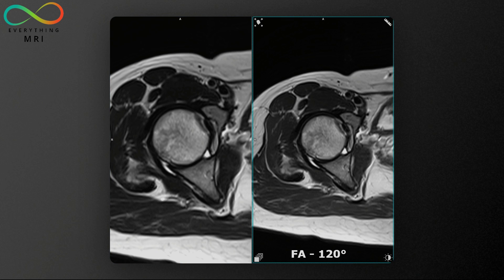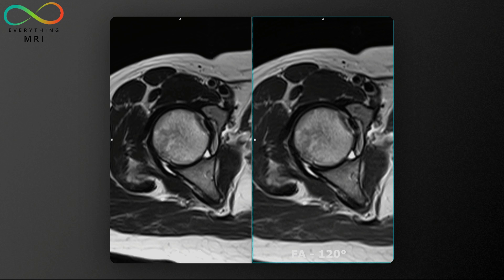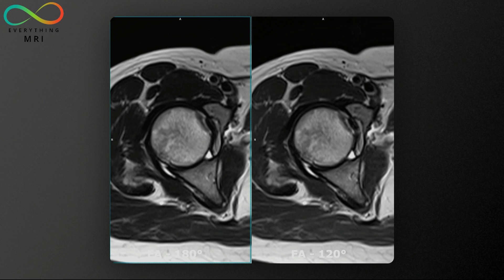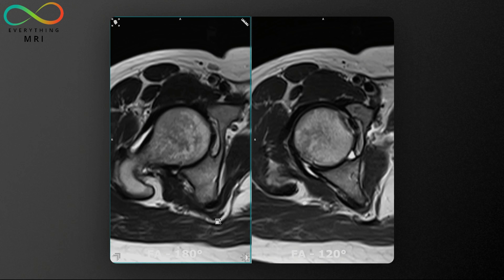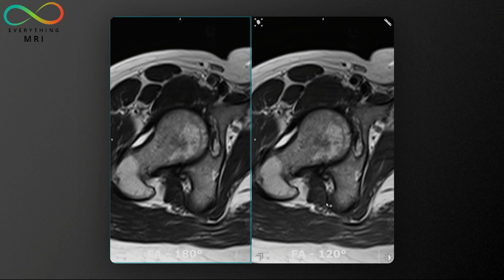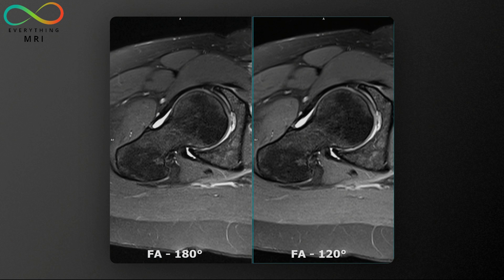There are no crucial differences in image quality between the TSE T2 acquired with a 180° flip angle and the one acquired at 120°. Similarly, comparing PD fat-sat sequences with different flip angles, there are some very mild differences in image quality and contrast. Overall, the benefits of lowering the flip angle for SAR reduction significantly outweigh these minor drawbacks. That said, I'm curious about your opinion — please leave a comment below.